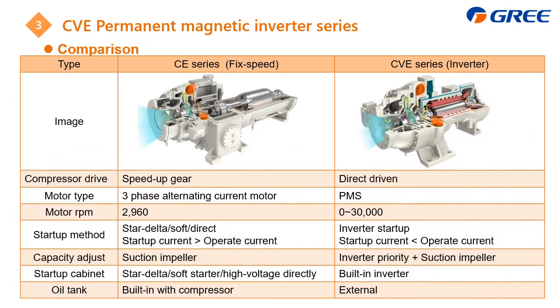This is the comparison between the compressors of the CE and CVE series. First, for the CE series, the compressor joint, we need to apply the speed-up gear for our desired RPM. And for the CVE, it is direct driven. Also, we adopt the PM motor, which for the efficiency is definitely higher. As for the RPM, for the motor here, the maximum is around 3000. But for the CVE, it is direct driven, which we can reach 30,000, ten times.